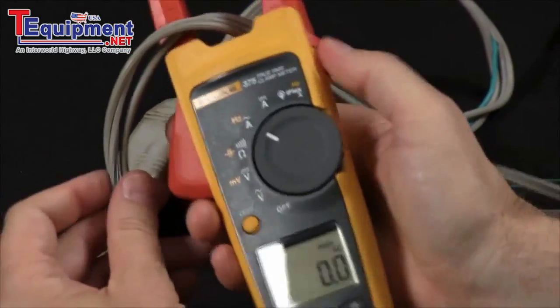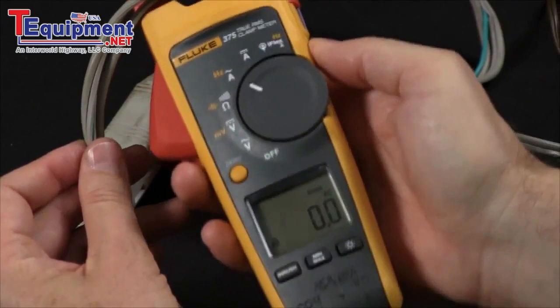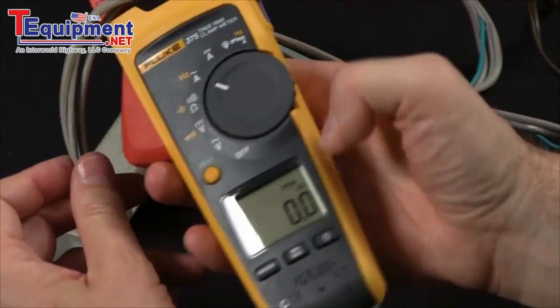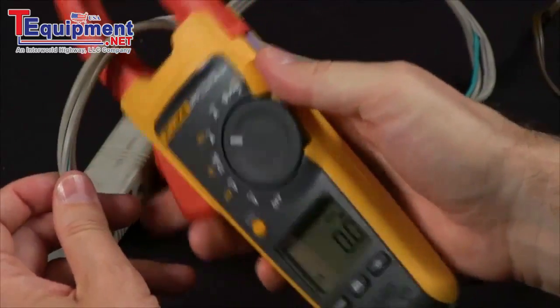A mistake that a lot of people make is trying to measure around the entire cord. You'll see that the flow going through the hot and returning to the neutral is going to cancel out, and we'll see a zero indication on the screen.